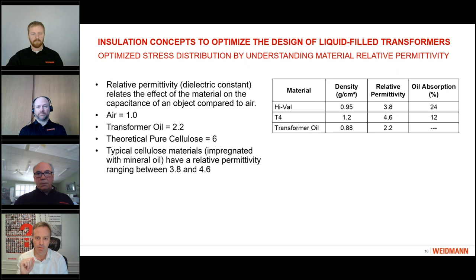It's an advantage. It's an advantage because whether it's ester liquid or transformer oil, the liquid is the weaker dielectric. So by having esters with a higher permittivity, you're able to move the electric stress into the solid insulation. So it's definitely an advantage.